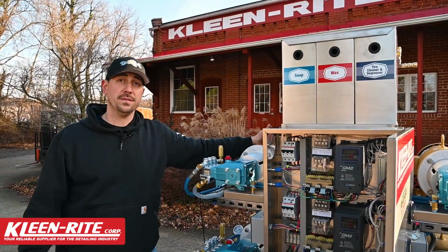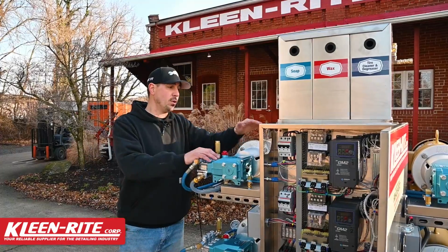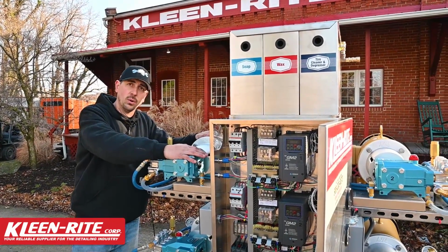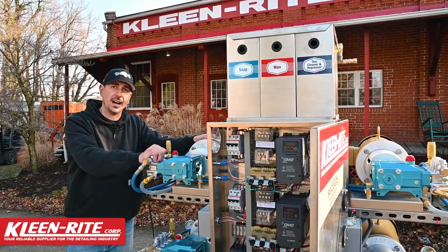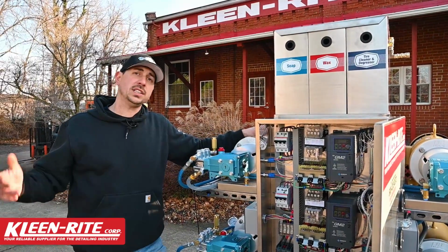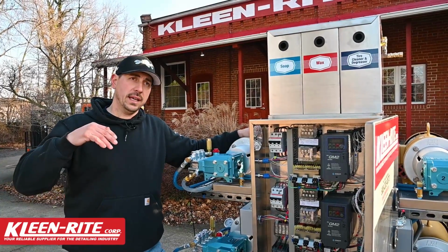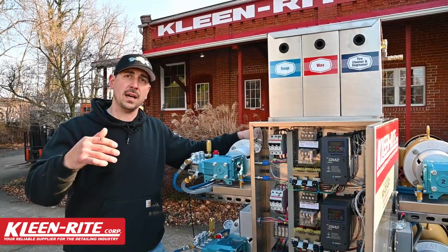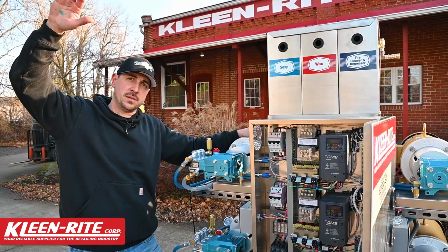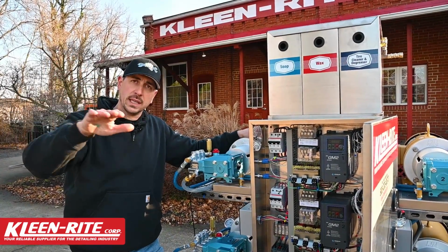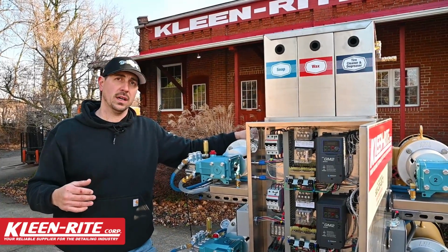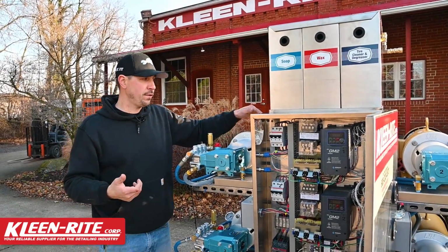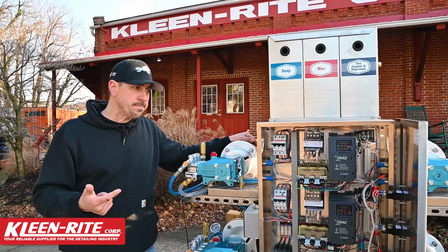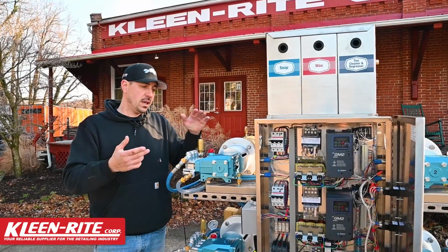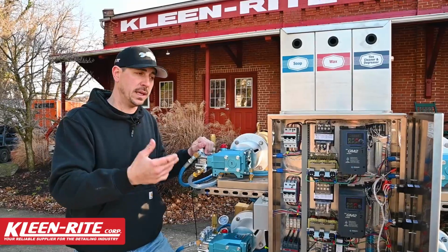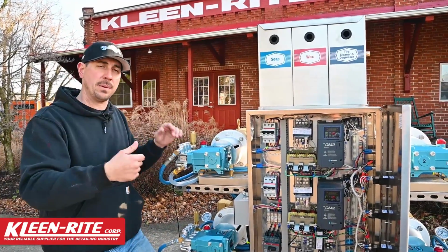Let's talk about some of the benefits of running a VFD on our pumps. The VFD helps us save on electric consumption, wear and tear on the pump, and wear and tear on the seals and valves as well. Why is that? Well, that's because we're ditching the old school mentality of using a contactor, which is taking the motor from 0 to 100% all the time, and we're actually smoothly ramping that motor up in speed and then decelling that motor slowly in speed as well. Now that does a couple things for us. It cuts down on in-rush electrical consumption for the motor, which is easier on the brushes in the motor, and it also saves on the banging of the pump itself starting up and getting up to speed.